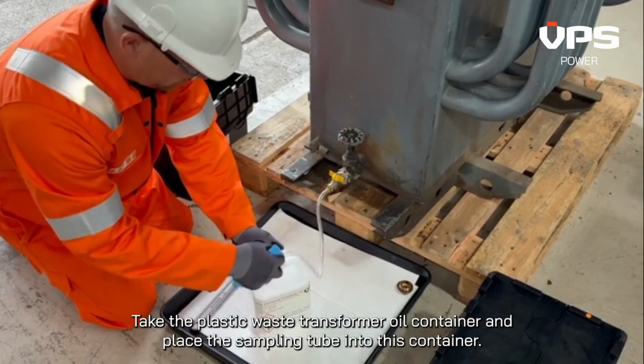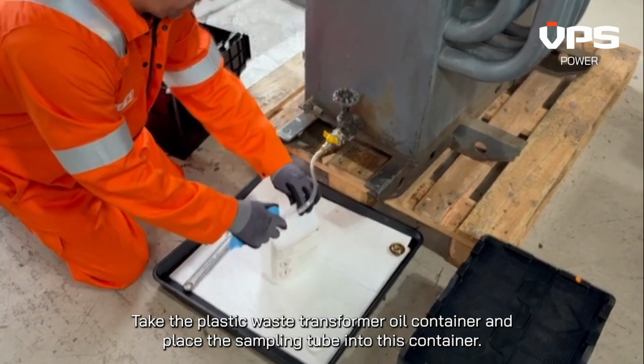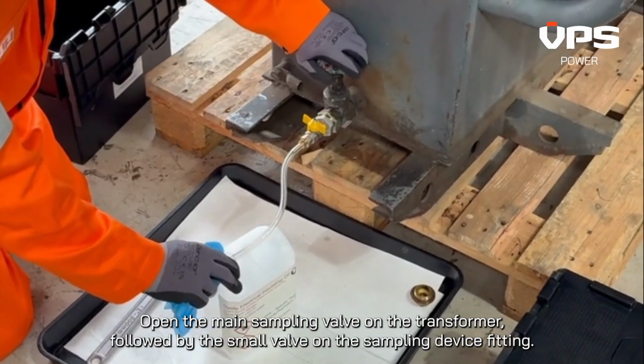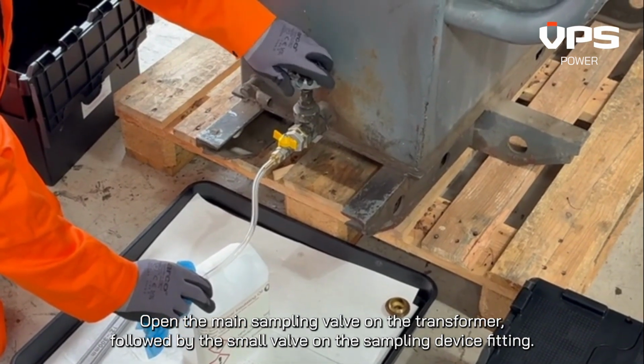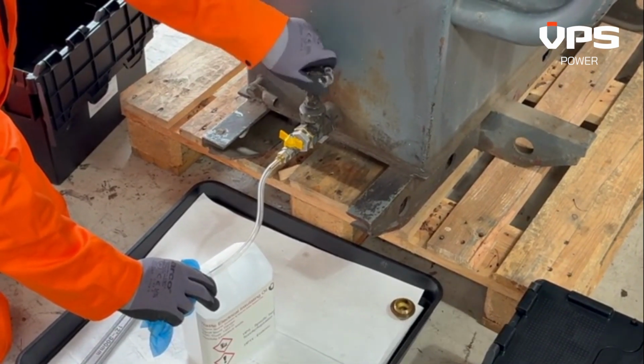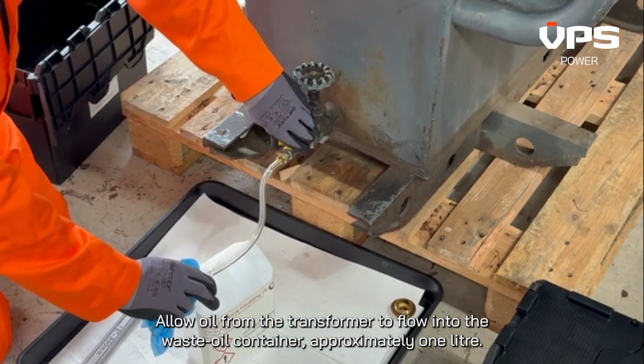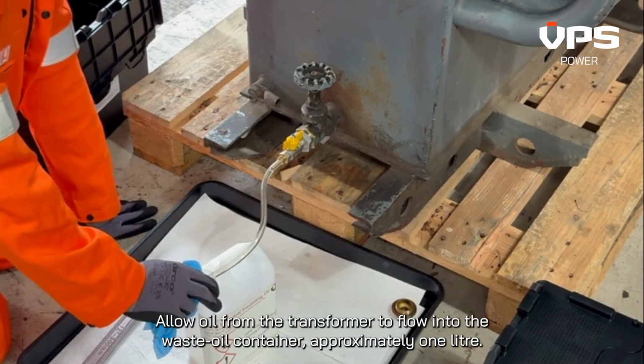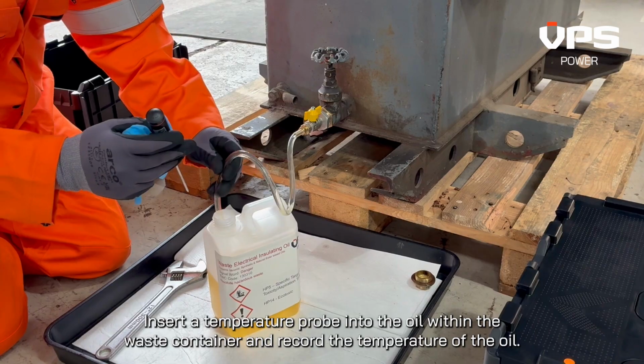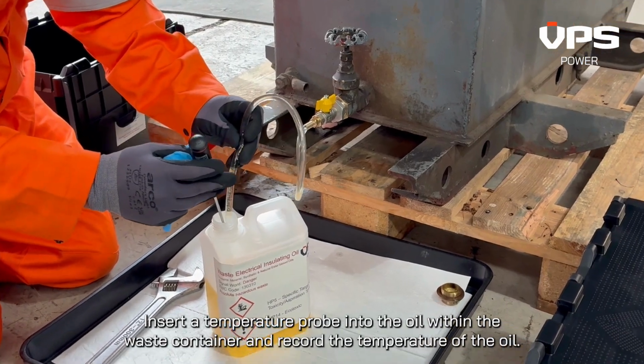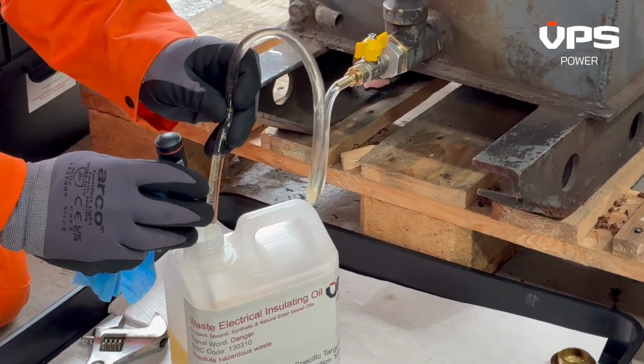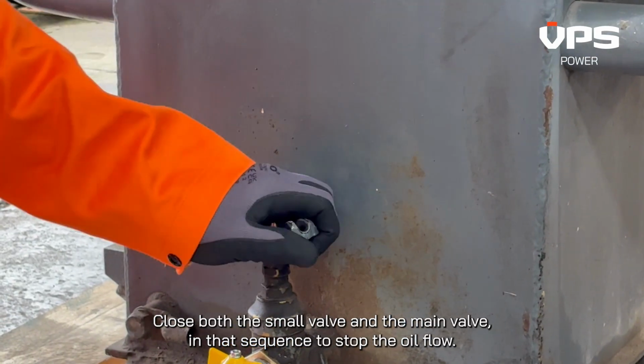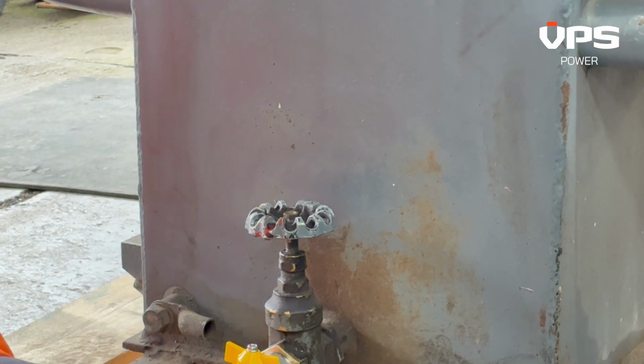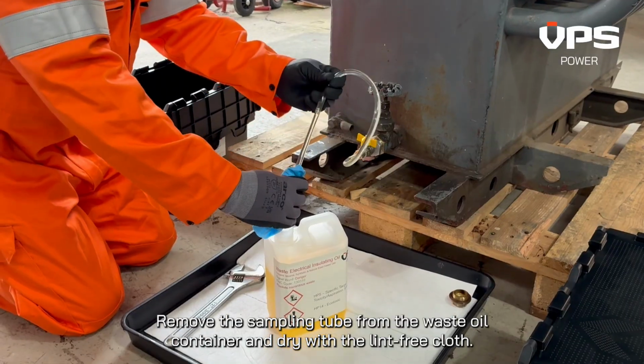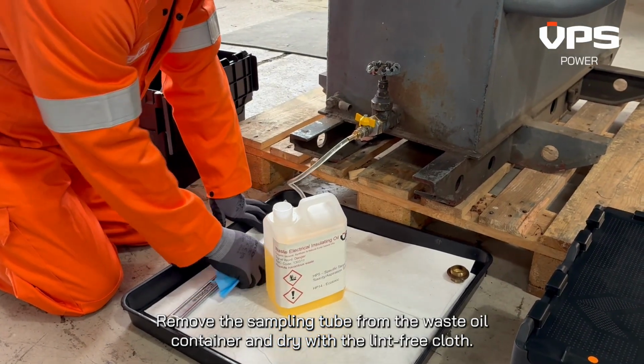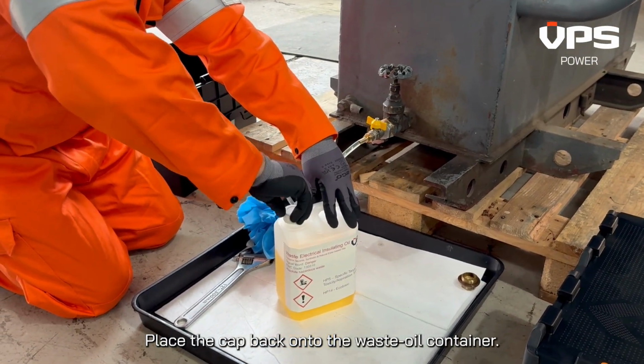Take the plastic waste transformer oil container and place the sampling tube into this container. Open the main sampling valve on the transformer, followed by the small valve on the sampling device fitting. Allow oil from the transformer to flow into the waste oil container for approximately 1 litre. Insert a temperature probe into the oil within the waste container and record the temperature of the oil. Close both the small valve and main valve in that sequence to stop the oil flow. Remove the sampling tube from the waste oil container and dry with the lint-free cloth. Place the cap back onto the waste oil container.